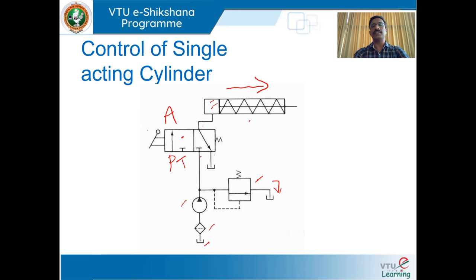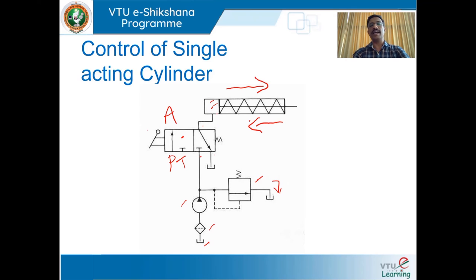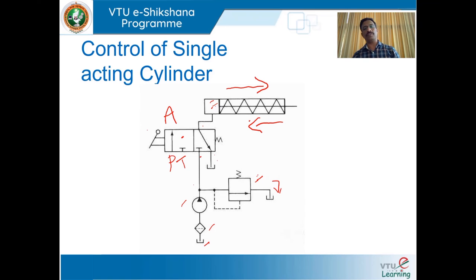When you release the lever, the valve will shift to the right envelope configuration — that is the spring offset mode. The cylinder will start retracting with help of the spring, and the oil present in the blank end is drained to the tank. During that operation, P is blocked and full pump flow goes to the tank via the pressure relief valve. This is how a three-way two-position valve is used to control a single acting cylinder.